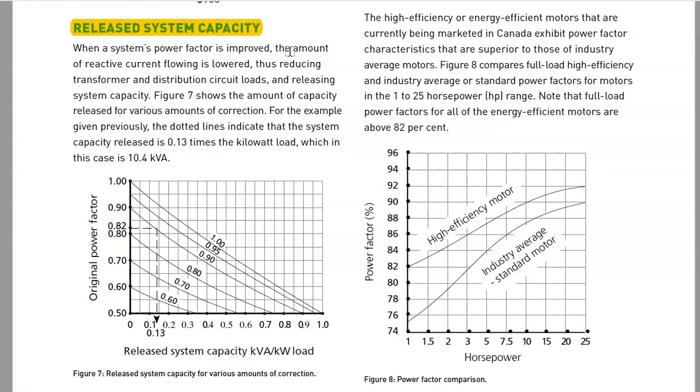All I had to do was go and rent that meter, put that meter on, leave it running for a week in their electrical room, come back, take a look at the readings, and I could see what I needed. And then it was just a matter of sending that off to power factor calculations. There's companies whose whole business is doing those power factor calculations.